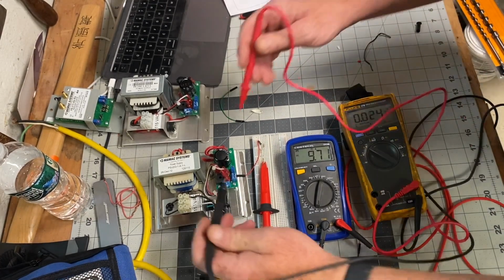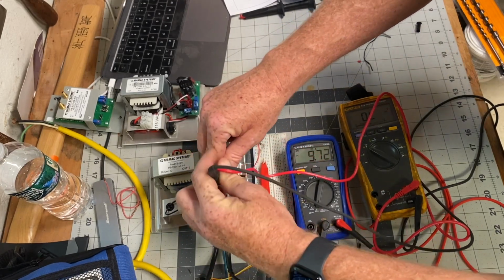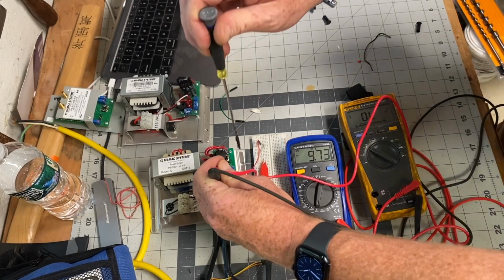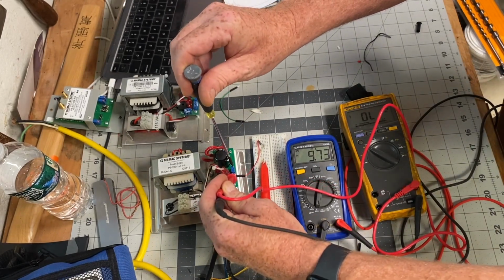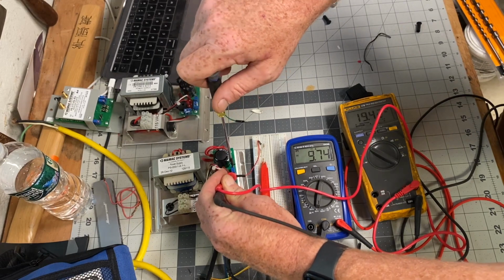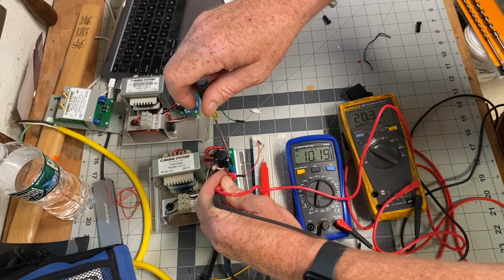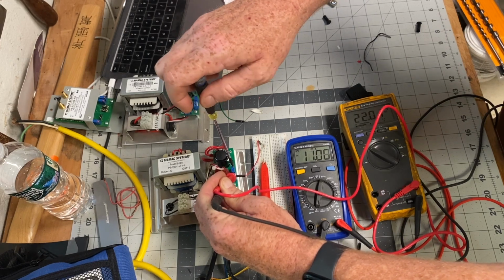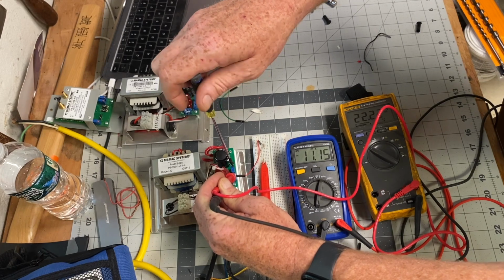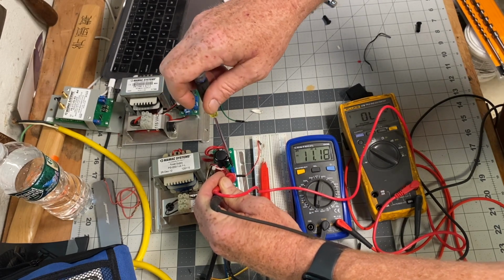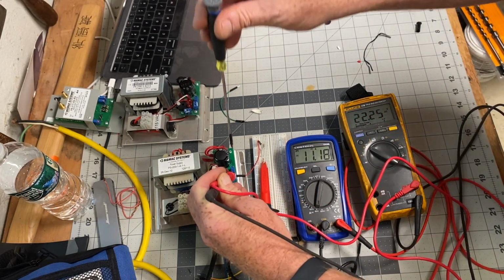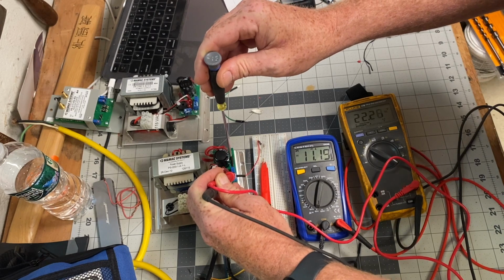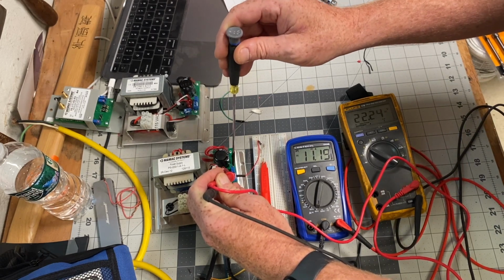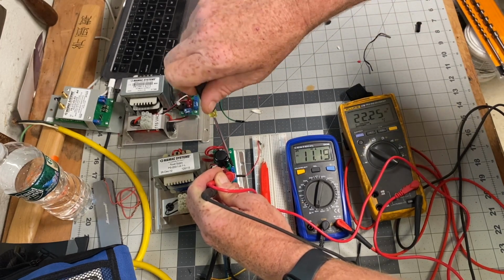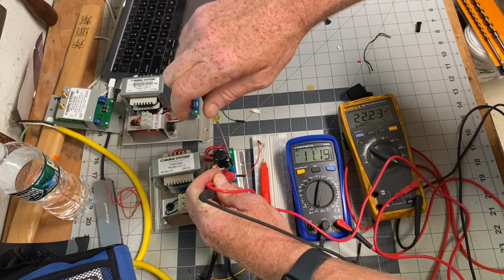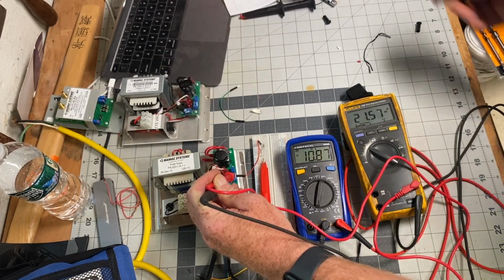Now, what I noticed with this is the pot really wasn't adjusted. So if I bring this back up to 24, can I bring it up to 24 volts DC? And if I do, will I get the milliamp reading I'm looking for? And so it's maxing out, right? I can't tweak it any further. I've got 22 volts DC coming off of this. The power supply just won't put out the power I need to get that reading. So I can't go up any higher. All right, let's tweak it until it's adjusted.